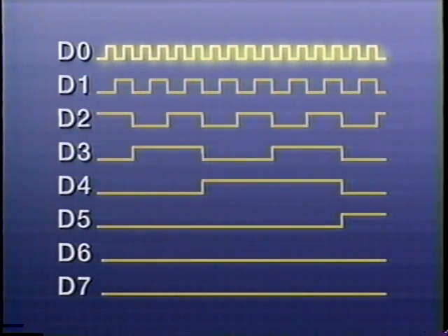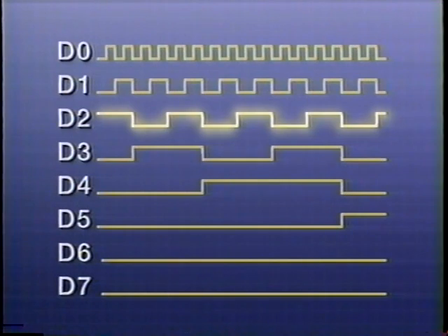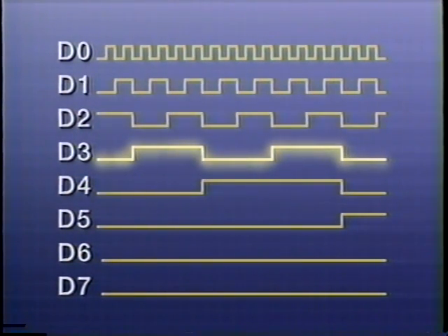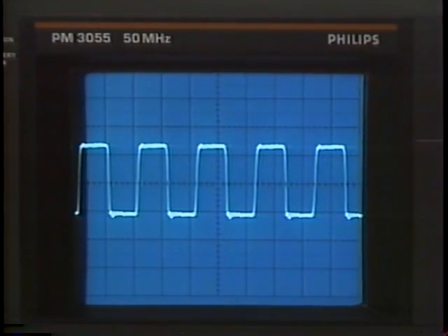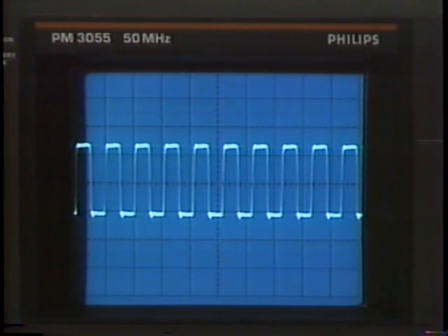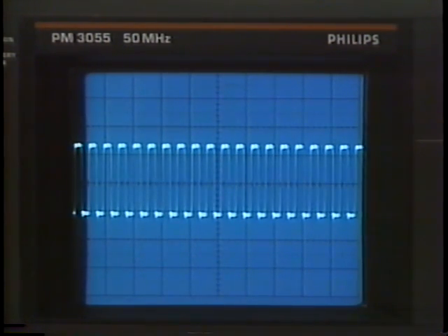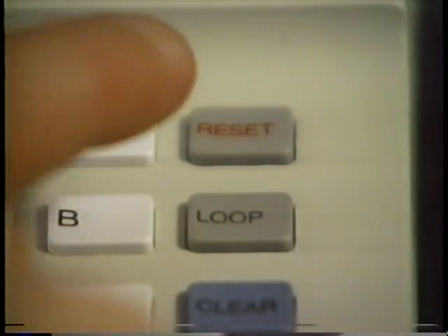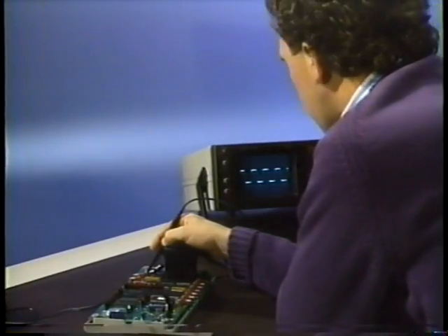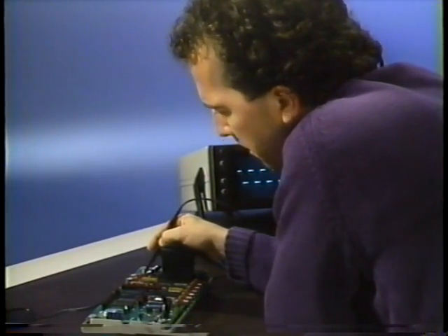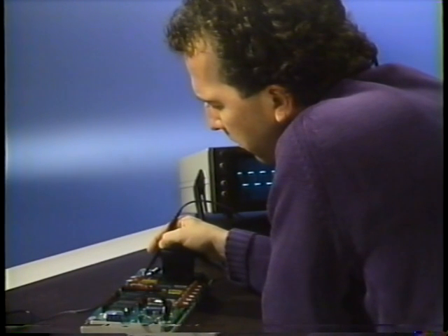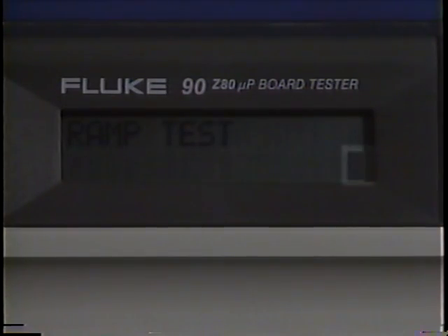The ramp test outputs an incremental bit pattern on the UUT address and data lines and performs a memory write cycle that enables any drivers, buffers, or address decoders on the UUT bus. This pattern can then be monitored with the Fluke 90 probe or with an O-scope. To run the test in a continuous mode, press Loop. This looping mode and all other activities or tests performed with the Fluke 90 is indicated by a flashing activity indicator in the lower right-hand portion of the display.